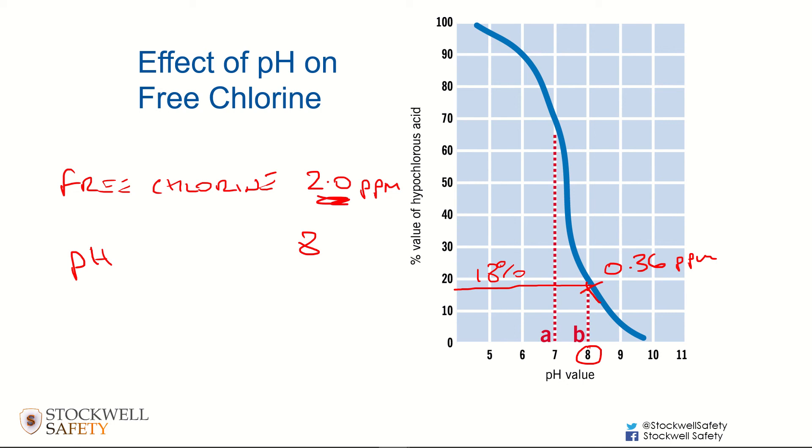You might have 2 showing up on your DPD1 tablet, but if you've got 8 showing up on your phenol red tablet test, then the effect of that is to render most of it useless, and only 0.36 of it is going to be doing any good in terms of killing bacteria and bugs.